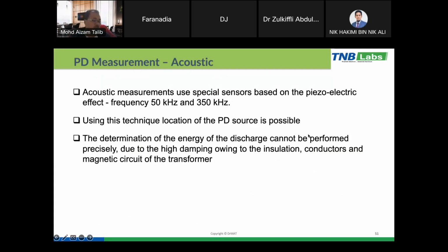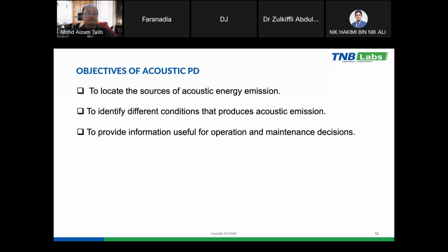Okay, the other method we can use is PD measurement using acoustic. Through this acoustic measurement, we use a piezoelectric sensor, where we put a sensor around the transformer. When the PD occurs in the transformer, it will generate sound. This sound will be picked up by the acoustic sensor. Through the different sensors, based on the time of arrival of the signal to each sensor, we are able to pinpoint the location of the PD.